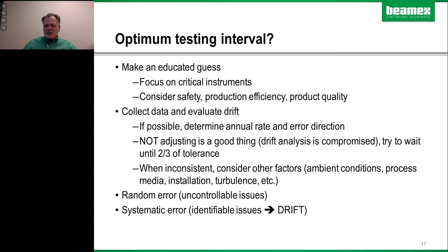So, when we talk about a testing interval, there's so many variables, and the best you can do to start is to make an educated guess. So, focus on your critical instruments. Consider all these factors, which will help you determine what's critical, and then, if you can collect data, you can start seeing if there is drift. If the instrument's not drifting, you can back off on your schedule. If you've got a real tight tolerance, maybe you need to tighten up on your tolerance. But one thing I tell our customers is that not adjusting is a good thing. If you go out and the instrument's in pretty good shape, maybe it's not perfect, leave it alone. If you can catch it until it's way out, then you adjust. So if you're always adjusting, then you'll never know how much that instrument is drifting.